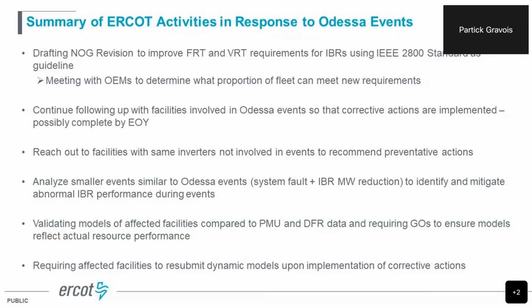The last part is really looking at the models. So we are validating the models of all these affected facilities against the PMU data and the digital fault recorder or relay data that we have. Anything that's not matching, we're requiring these GOs to go look at these models and make sure they're actually reflecting their actual resource performance. And any of these that are implementing these corrective actions, we're requiring them to make these changes in their models and resubmit those dynamic models as well. And I believe that is it.